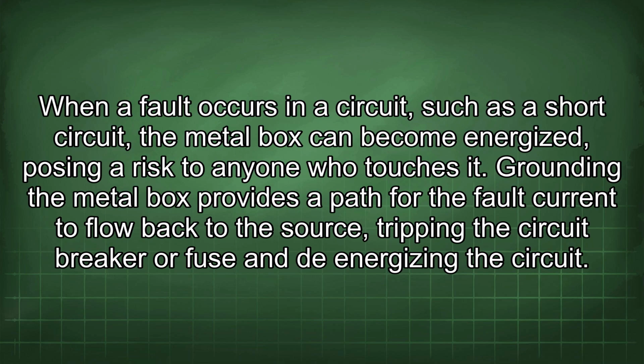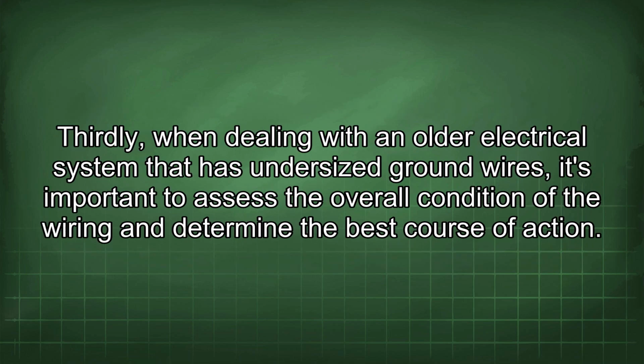When a fault occurs in a circuit, such as a short circuit, the metal box can become energized, posing a risk to anyone who touches it. Grounding the metal box provides a path for the fault current to flow back to the source, tripping the circuit breaker or fuse and de-energizing the circuit. Thirdly, when dealing with an older electrical system that has undersized ground wires, it's important to assess the overall condition of the wiring and determine the best course of action.